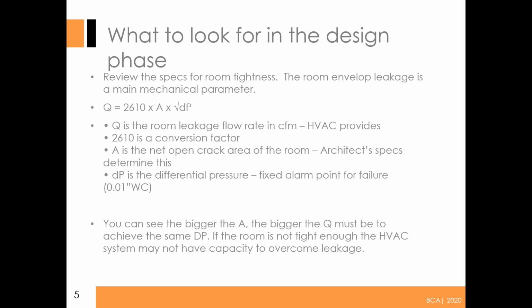The one thing I also caution is don't get tied up with an engineer trying to calculate this, and then he puts in a transfer grill or something the size of A. Now, A is not really calculable. A is pretty much what you have when air moves through all the materials, every crack in the drywall, every conduit that's not fully sealed, all that stuff. It's impossible to really calculate. So my main takeaway is you can see the bigger the A, the bigger the Q. So the room is not tight enough. The HVAC system may not have the capacity to overcome the leakage.